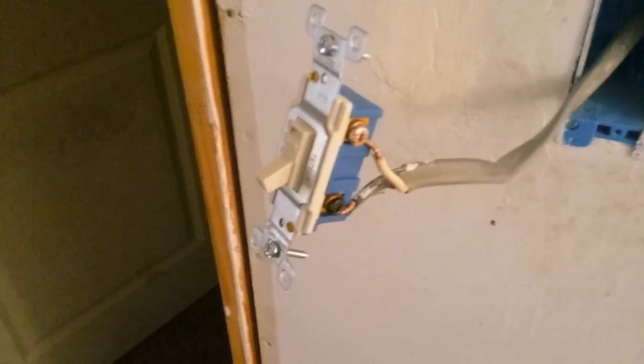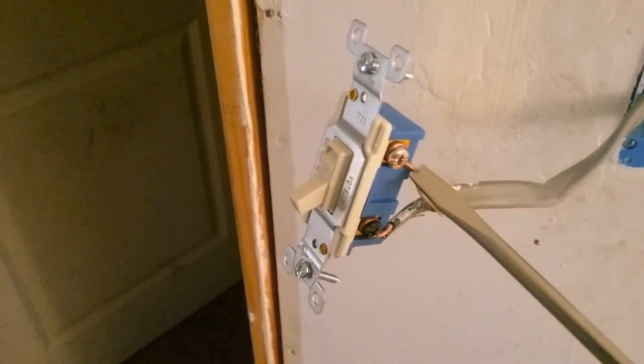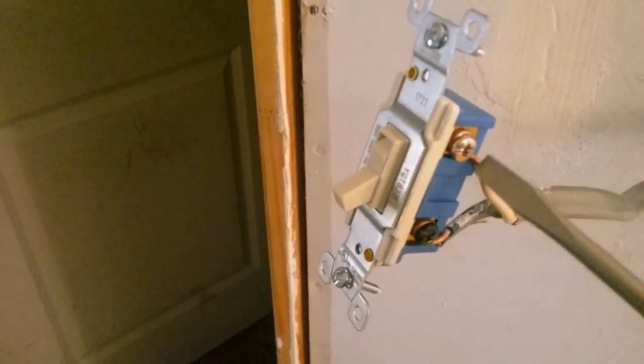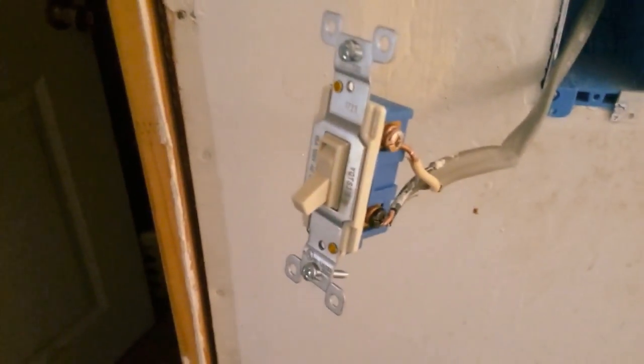Okay, here I am again. So I've taken the old switch off, and all I've done is, this would be my traveler wire, this would be my hot one. And since there's only two wires here, no ground or nothing, this is the only two I have hooked up. Now let me say something. When you put these wires, let me show you this switch. You're able to backstab it, which is those holes right there. I hate backstabbing. Don't use it.